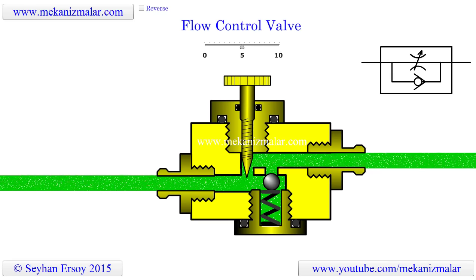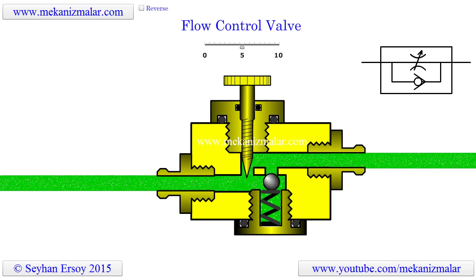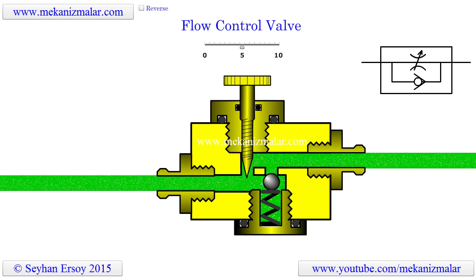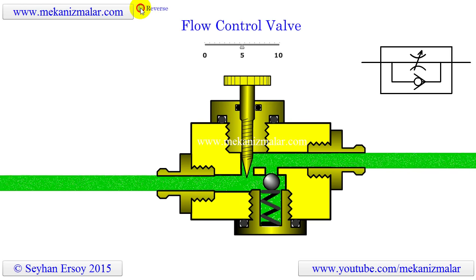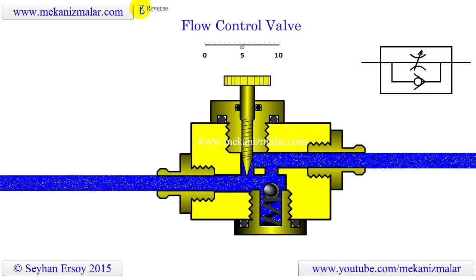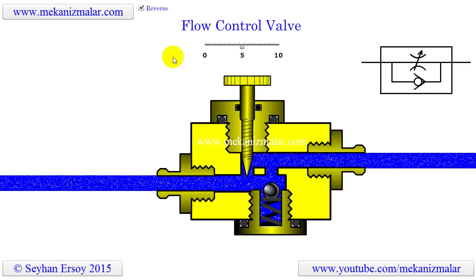You can solve this problem by adding a quick exhaust valve at the inlet port of your cylinder. I will do an animation of this in the near future. The other solution is to put a check valve in tandem with a needle valve such that the check valve will be open in the return stroke of the piston. The uncompensated flow control valve we are going to describe here is actually a repackaging of the needle valve and check valve combination in a single valve.